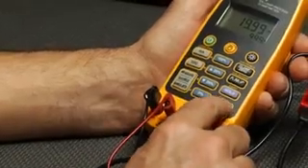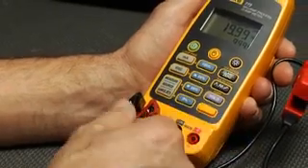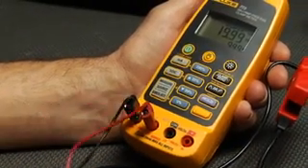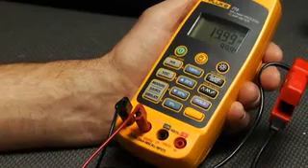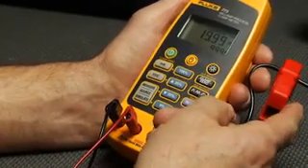In milliamp scaling mode, you can connect the logging DMM to the 773 output and troubleshoot intermittent signal problems without breaking the loop by logging the milliamp output signal.